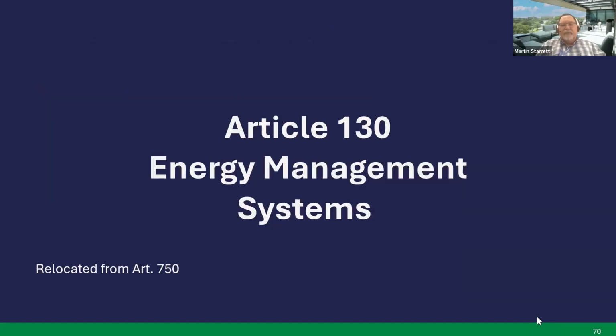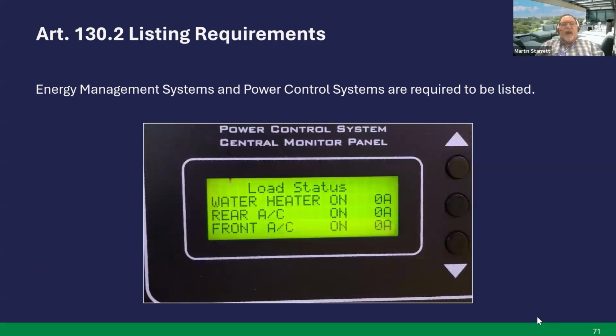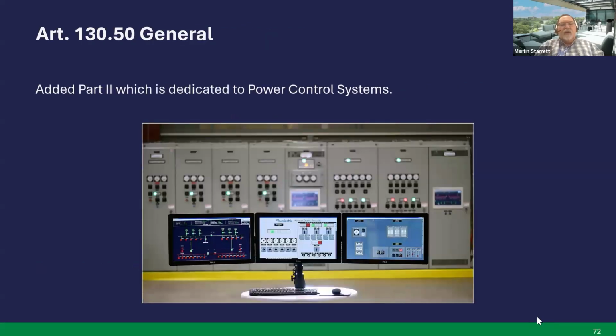Article 130, Energy Management Systems. This was relocated from Article 750. Article 130.2, listing requirements. Energy management systems and power control systems are required to be listed, and those requirements will be found in that article. Next slide. Article 130.50, general. The added Part 2 to this article is now dedicated to power control systems, so all the requirements for those will be found in Part 2.